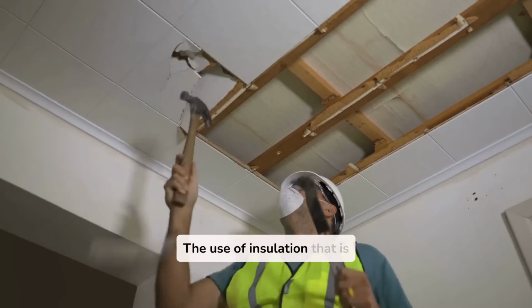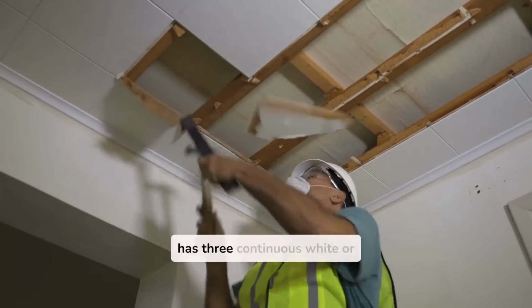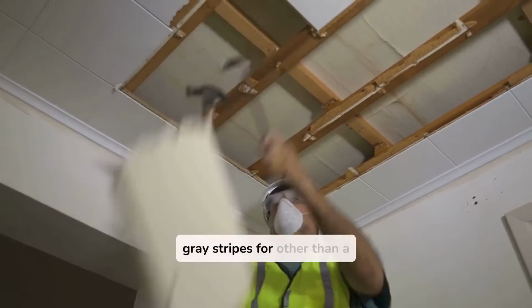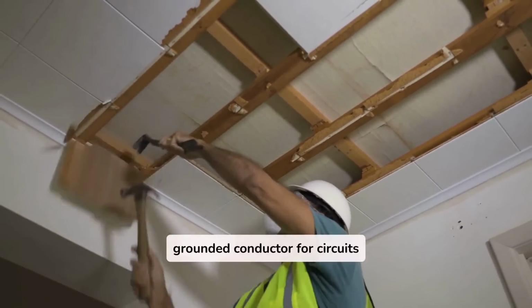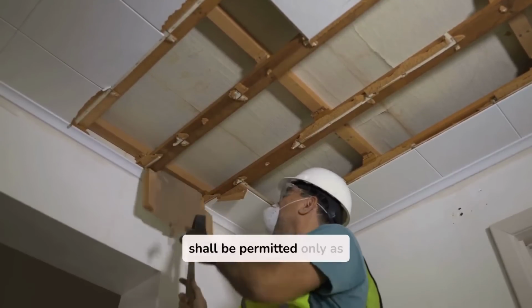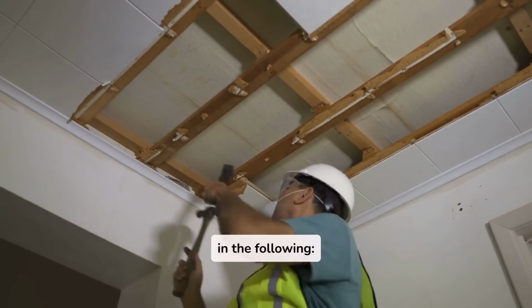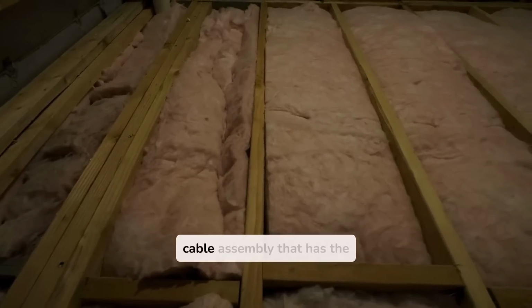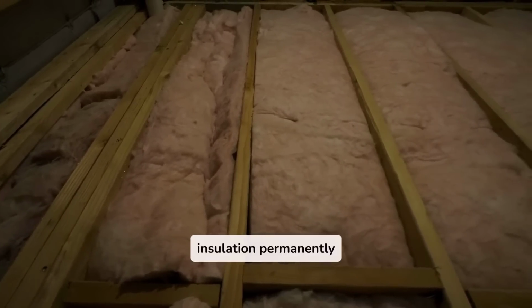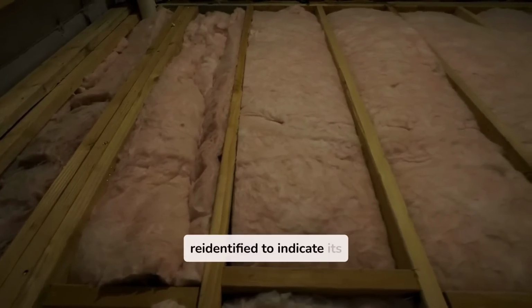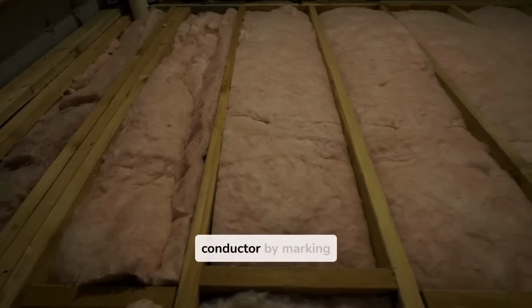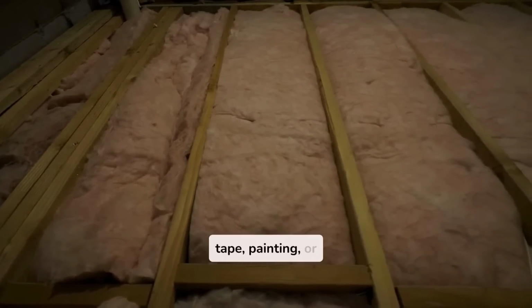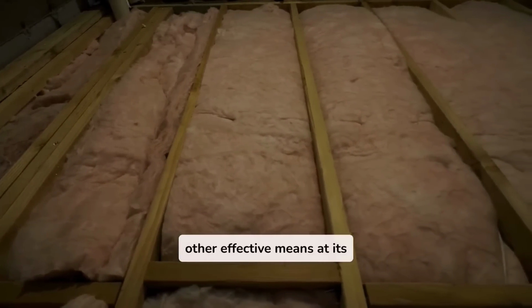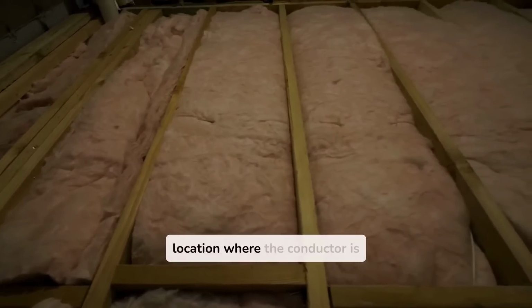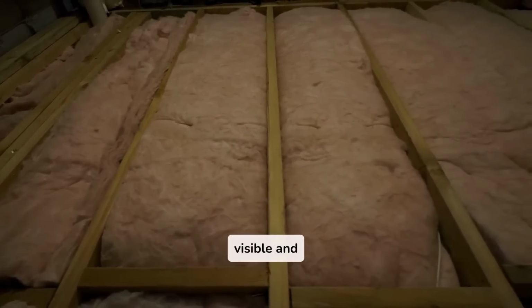C. Circuits of 50 volts or more. The use of insulation that is white or gray, or that has three continuous white or gray stripes for other than a grounded conductor for circuits of 50 volts or more, shall be permitted only as in the following. 1. If part of a cable assembly that has the insulation permanently re-identified to indicate its use as an ungrounded conductor by marking tape, painting, or other effective means at its termination, and at each location where the conductor is visible and accessible.